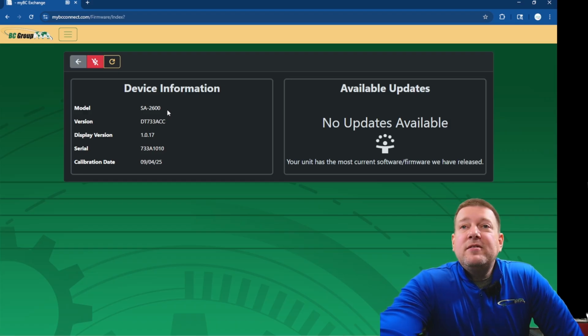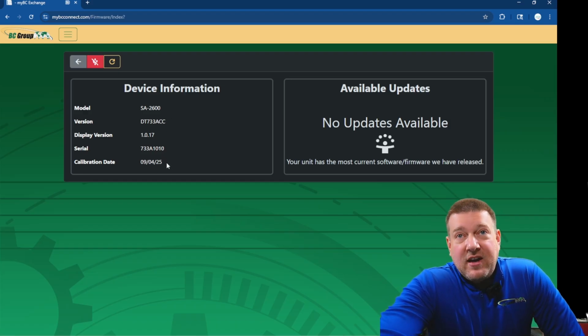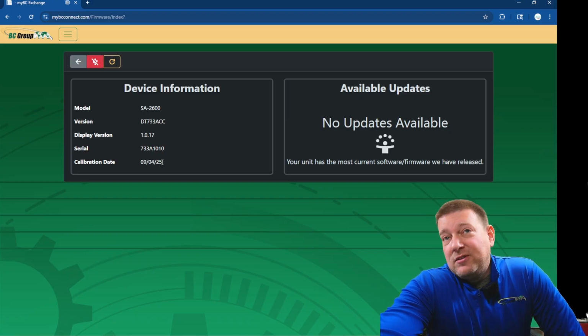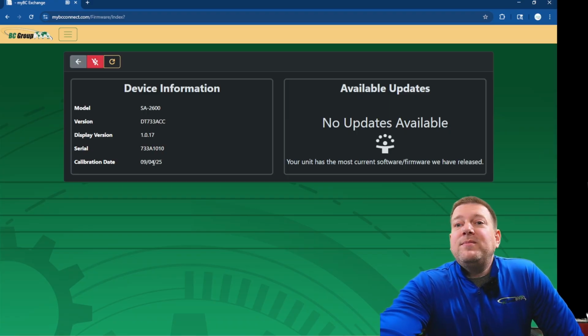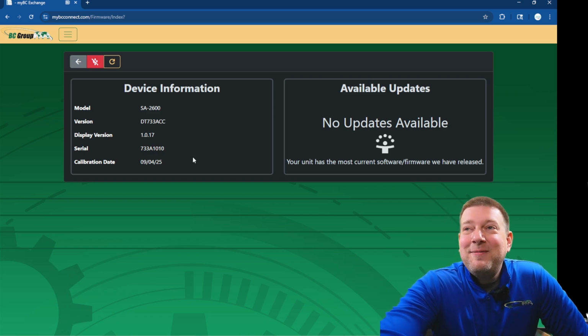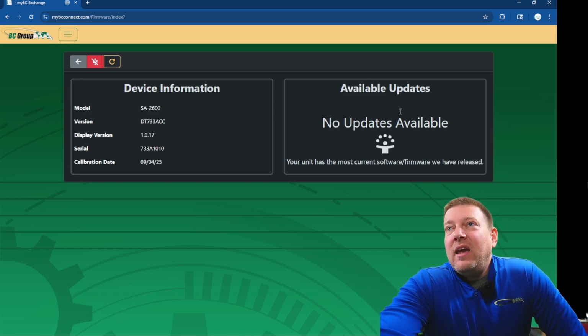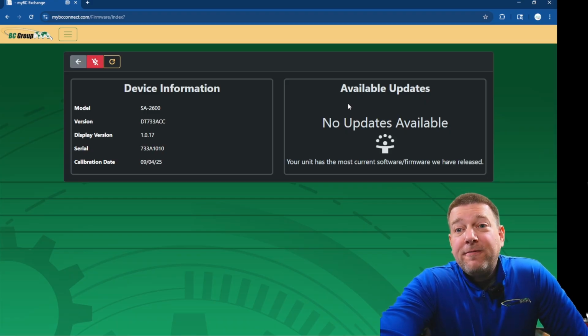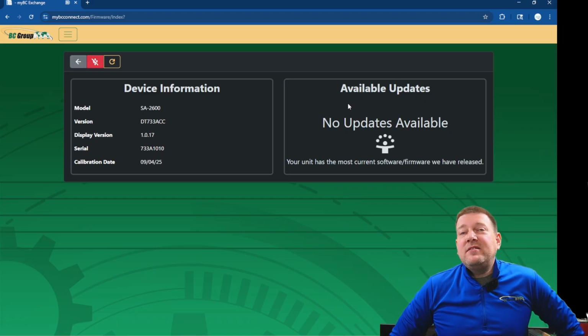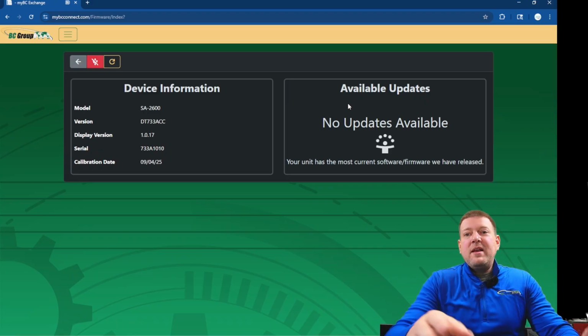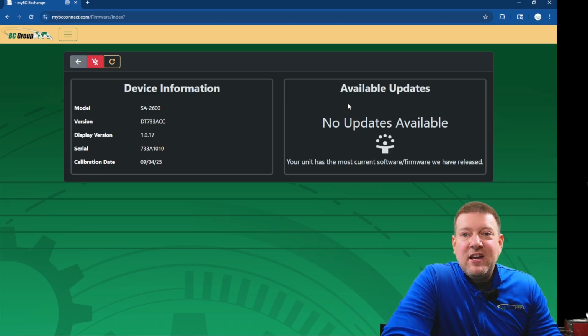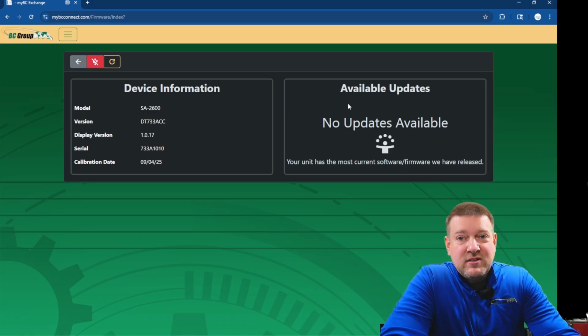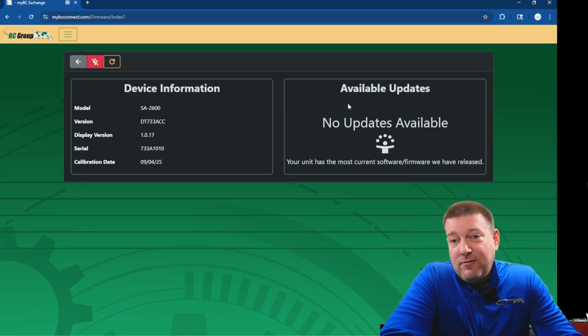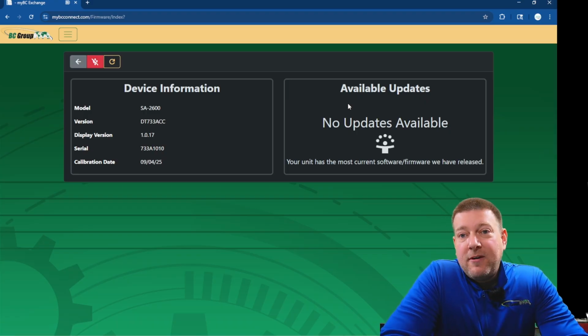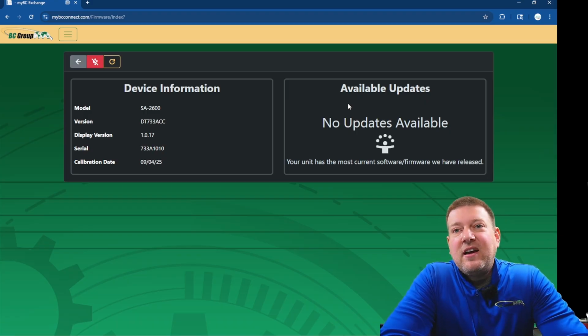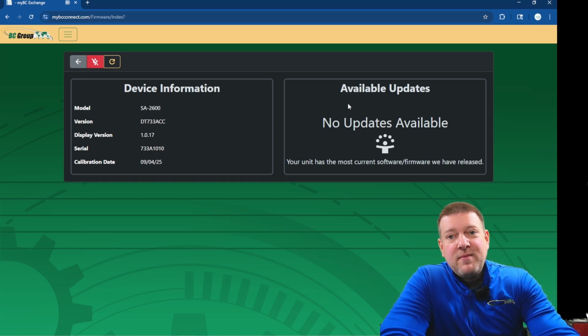Okay, and this is very important. You always want to make sure that your test equipment is calibrated, to which you can see mine is actually due this month. I have until tomorrow. So tomorrow I will have an error code on my electrical safety meter, and it will now be due for calibration. And over here on the right hand side, if you have any available firmware updates, it's going to signify right there, and it's going to ask you if you want to update your firmware. Now, many manufacturers, if you want to update your firmware, you have to send the device into a depot where they will charge you for the service and/or they're going to repair the device and charge you for the repair. We allow you to modify the firmware on your devices by going into mybcconnect.com and just connecting it with a USB cord, and you're ready to go.